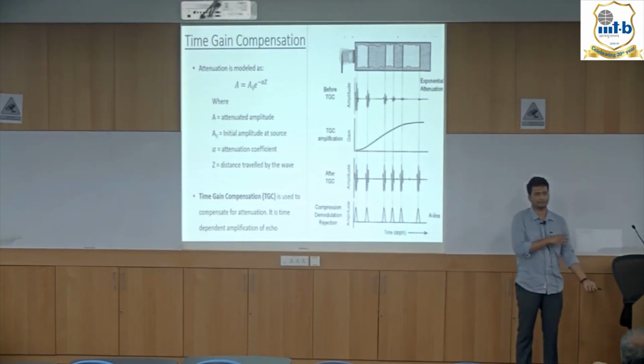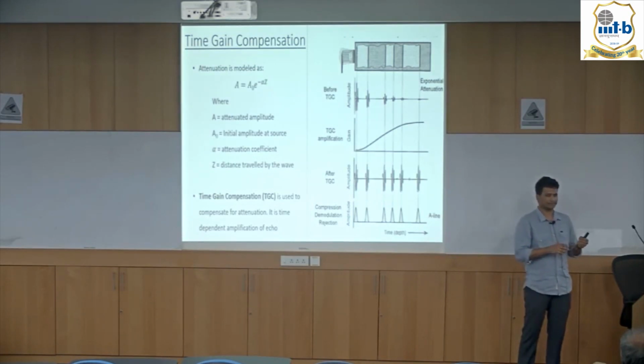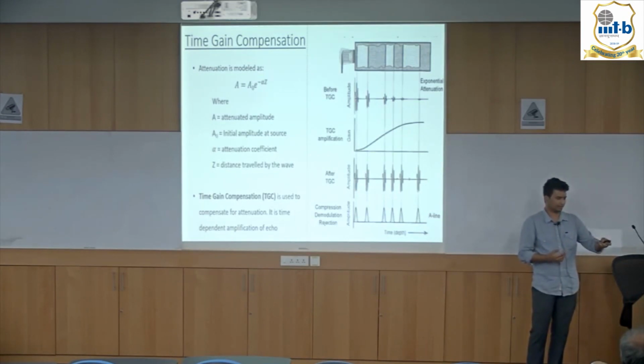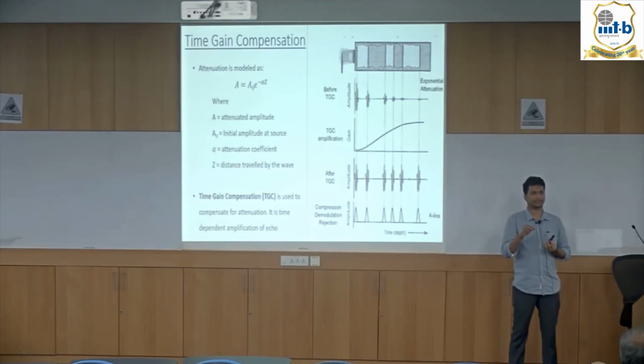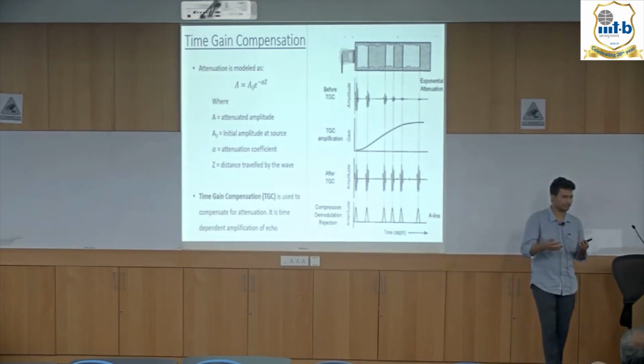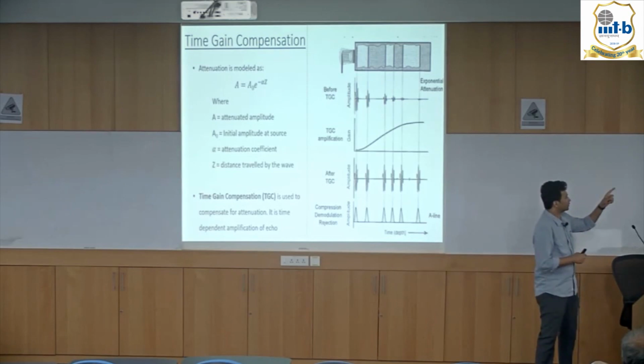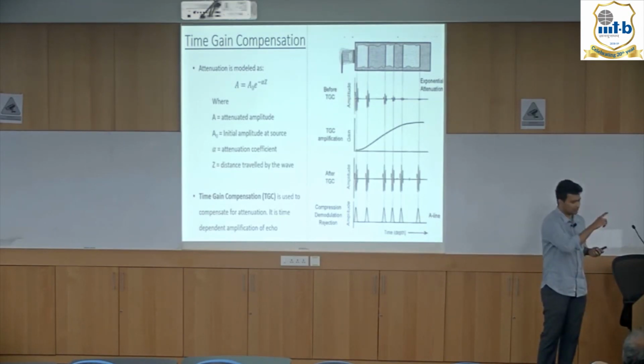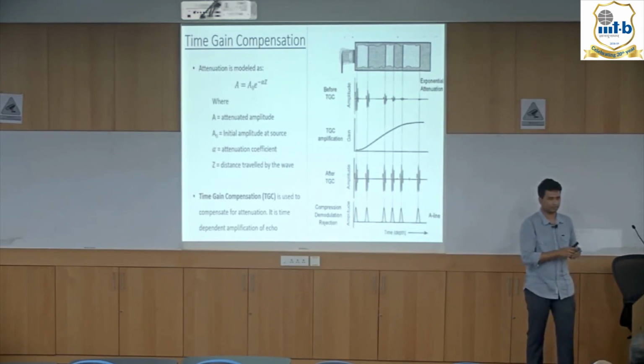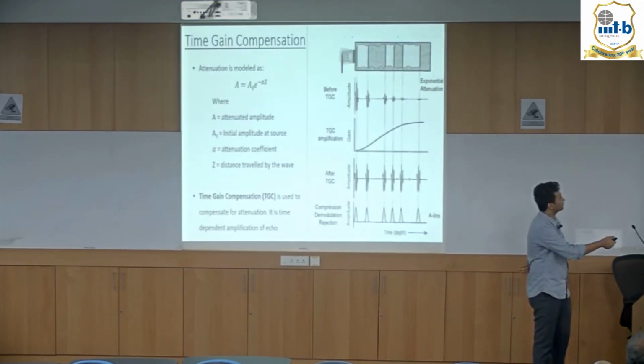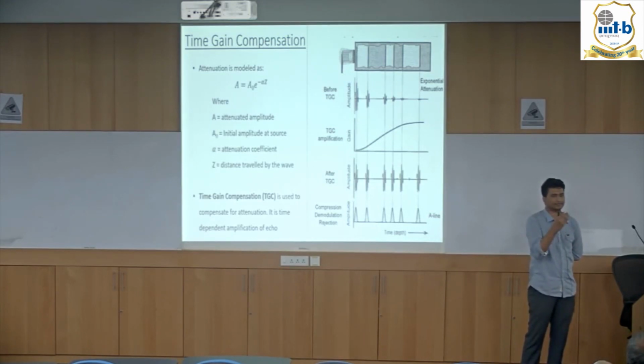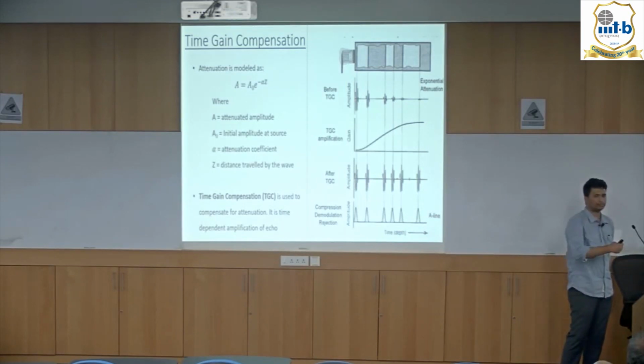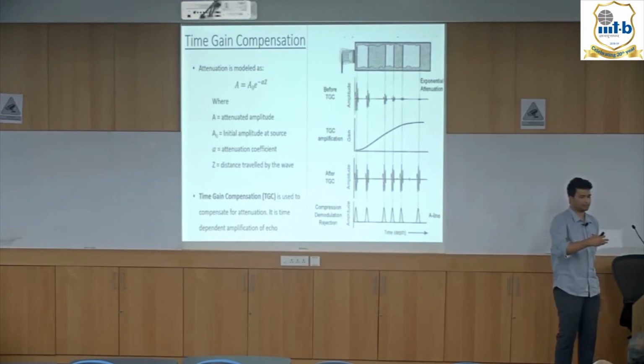Attenuation is modeled by observation. It has been modeled as having an exponential nature, no matter through which material or what the medium is made of. There is a parameter called alpha, the attenuation coefficient, which characterizes a medium. Different mediums have different alpha values, but they all provide exponential attenuation. You can see at the top of the diagram the interfaces between the light gray and the dark gray regions. They all have the same differences in acoustic impedance, but their corresponding received echoes are of lower amplitude. That is because of the attenuation offered by the medium the echo has to travel through.